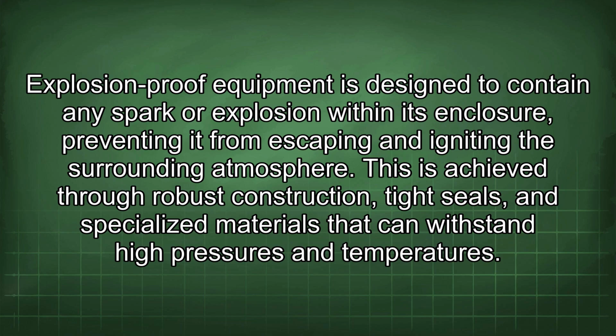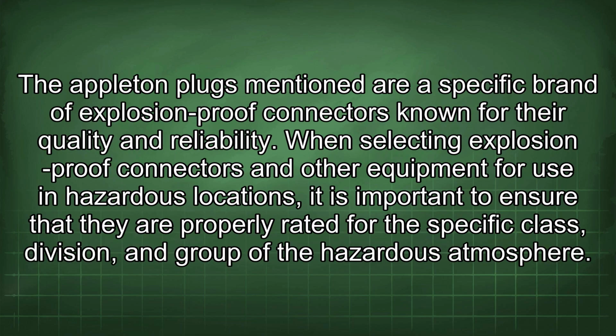Explosion-proof equipment is designed to contain any spark or explosion within its enclosure, preventing it from escaping and igniting the surrounding atmosphere. This is achieved through robust construction, tight seals, and specialized materials that can withstand high pressures and temperatures. The Appleton plugs mentioned are a specific brand of explosion-proof connectors known for their quality and reliability.